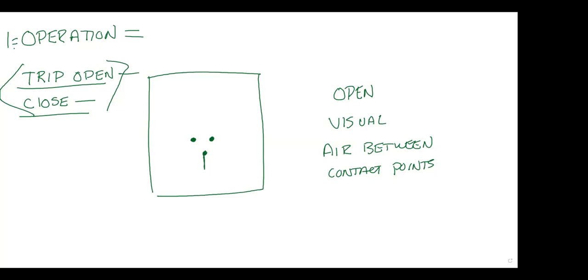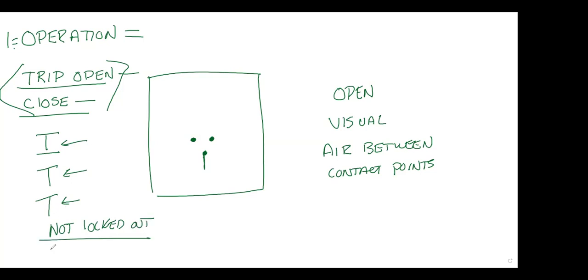I don't need to take the breaker to lock out. What takes the breaker to lock out? As explained yesterday, an I and what? It took an I, by the way I explained it yesterday, and 2 T's to take the breaker to lock out. Right? I don't want the breaker to go through the I, T, and T. I want it to go to I open immediately. So it's I, instantaneous, and does not reclose, not locked out. Okay. Questions there, concerns? All right. Let's get rid of that one.